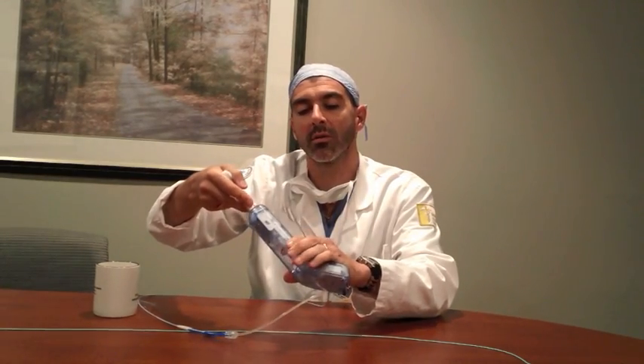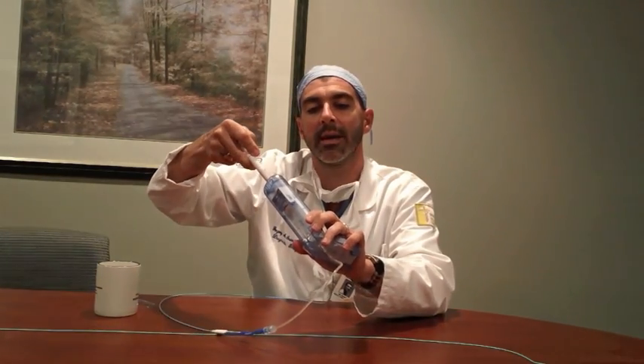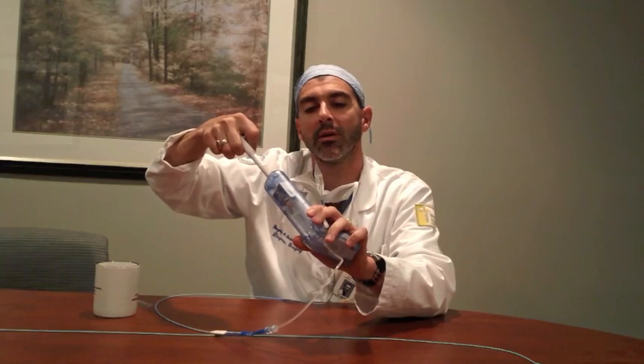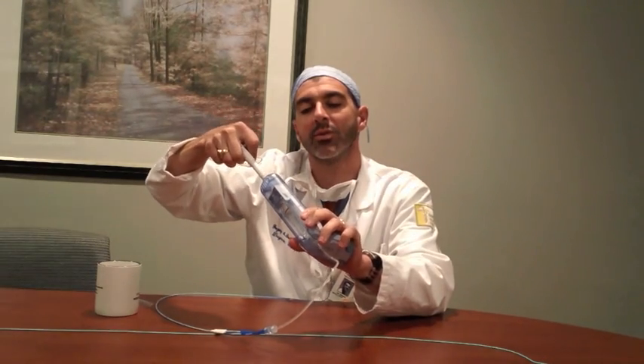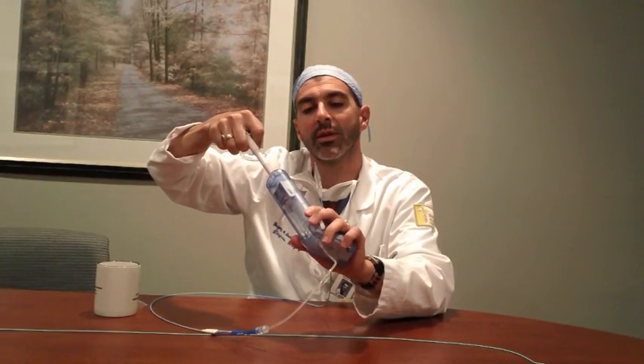And when the balloon gets to the pressure it needs to be at to open up the narrowing, it is cracked or permanently stretched. Often that's at a valve level. When we get done, we release the pressure on the balloon and remove the balloon fluid, bringing the balloon back down to its original state without any of the fluid inside.